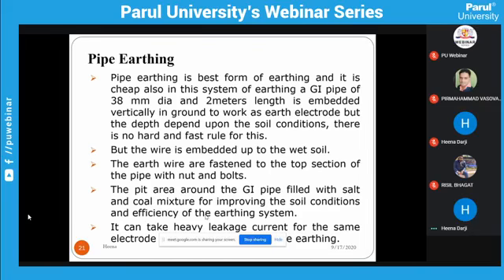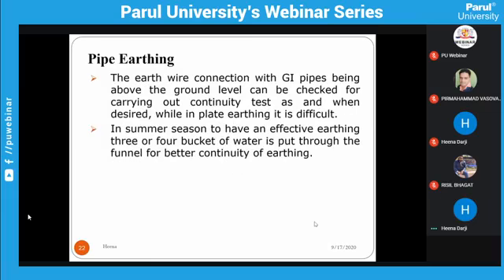of the earthing system. It can take heavy leakage current from the same electrode size in comparison to the plate earthing. The earth wire connection with GI pipes, being above the ground level, can be checked for carrying out a continuity test when desired, while in plate earthing it is difficult.